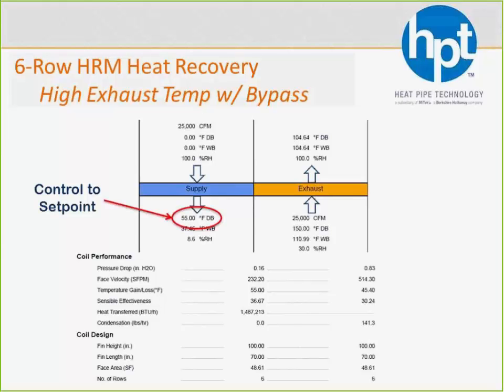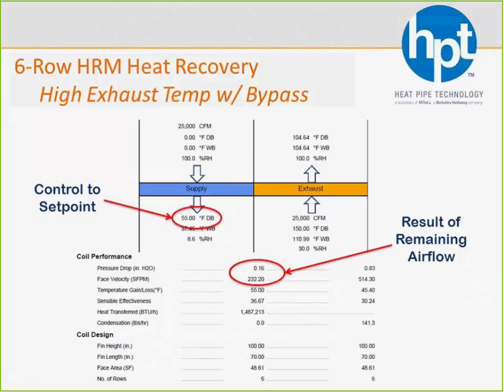Now you'll find that within Select Plus, on the exhaust side, we're still showing that 514 feet-per-minute face velocity because we still have all the air going through the exhaust side, but now we're bypassing around the supply side. So you can actually see that the resulting air that's going through the heat pipe that's not being bypassed has a lower face velocity and therefore a lower pressure drop as well. So those numbers are showing you what's actually going through the heat pipe to hit that temperature, and you can plug that in as well, to say what temperature to go to and control to that certain set point.